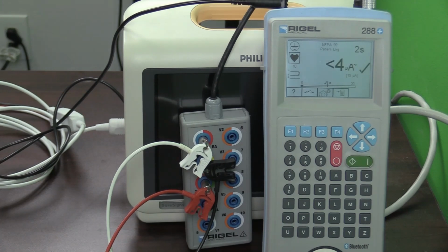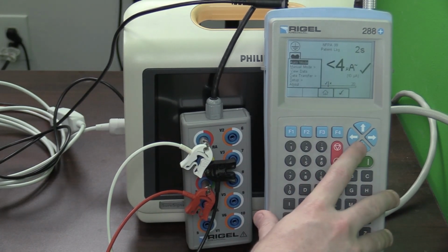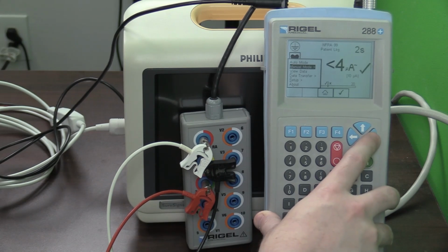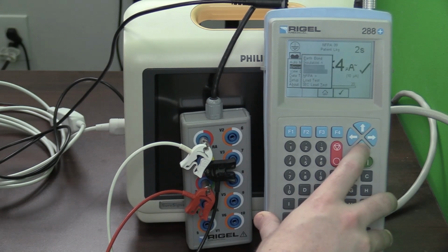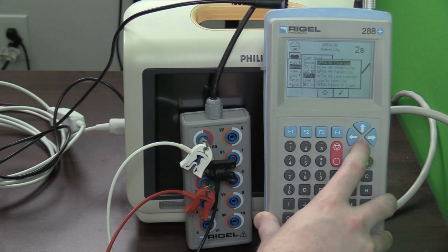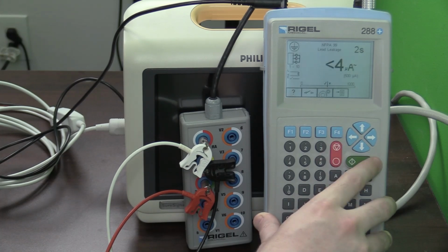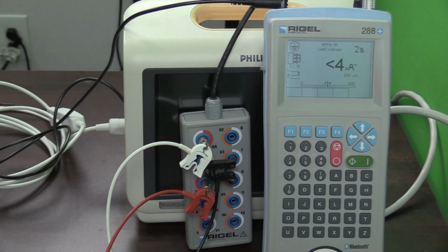Now we can select F4 to open up the menu, go down to manual mode, and this time we are going to scroll down to lead leakage, select F4, and hit the green button to run the test. And right now we're getting a reading of less than 4 microamps. And when the check mark pops up on the screen, that means the device has passed the test.